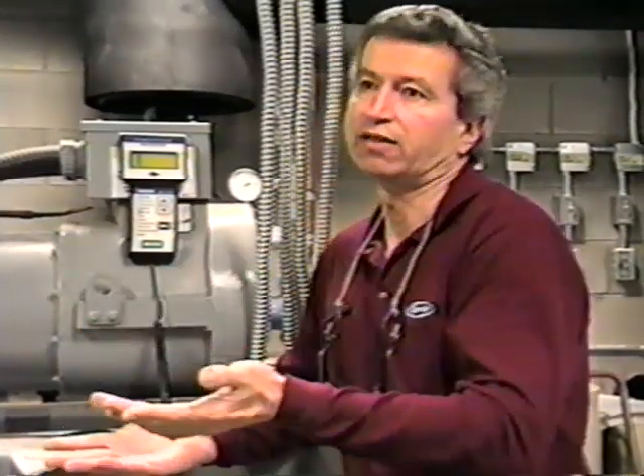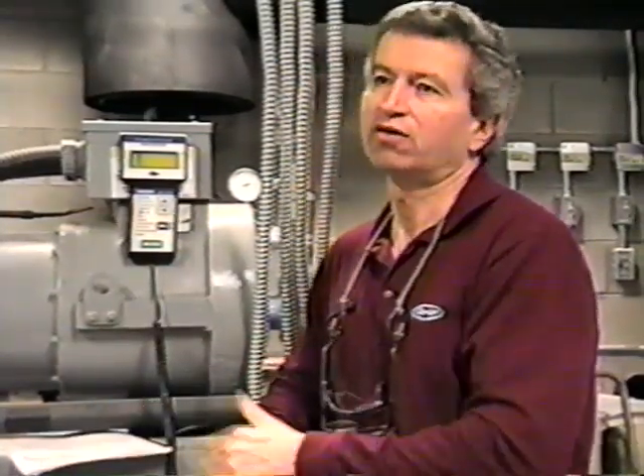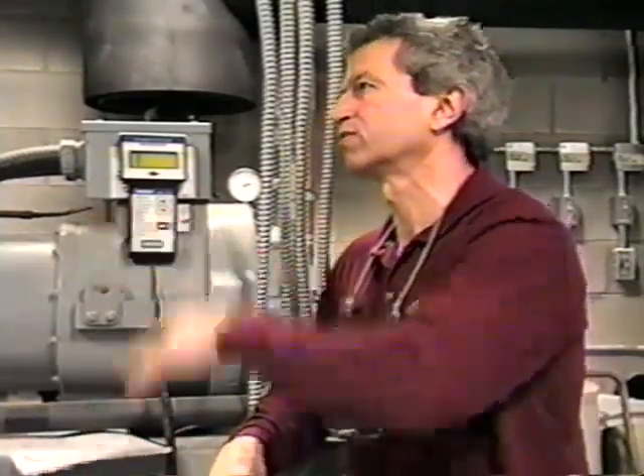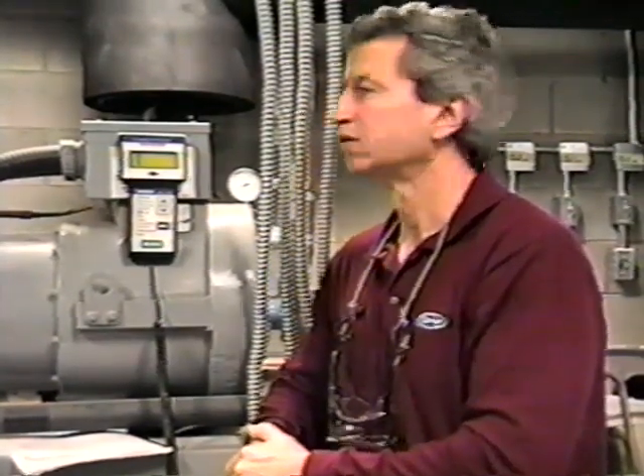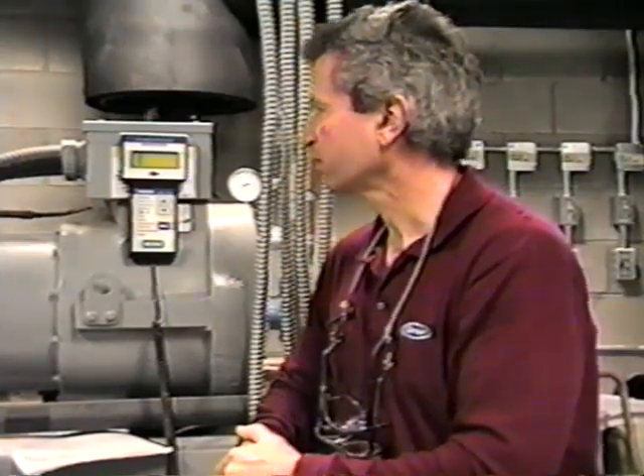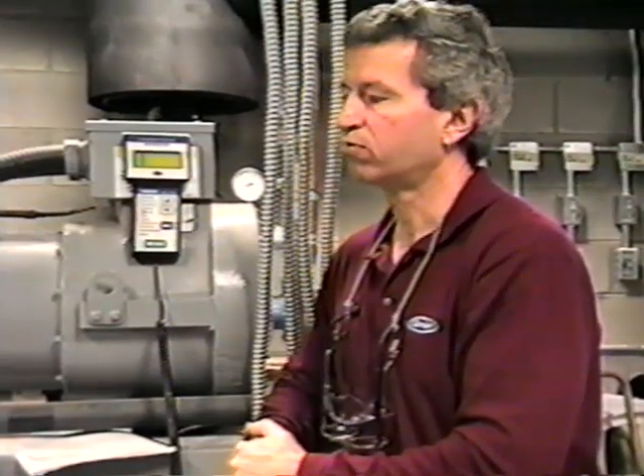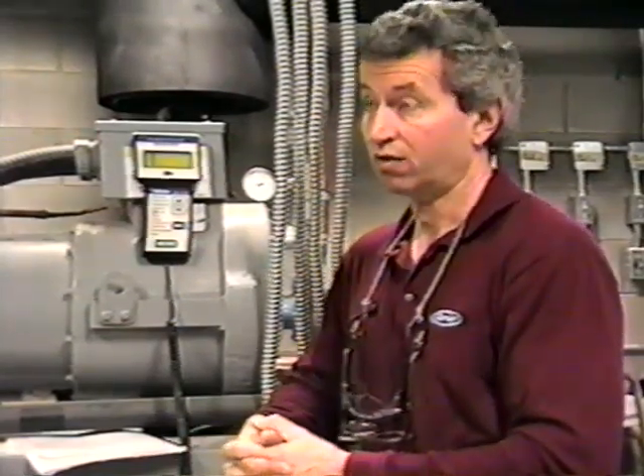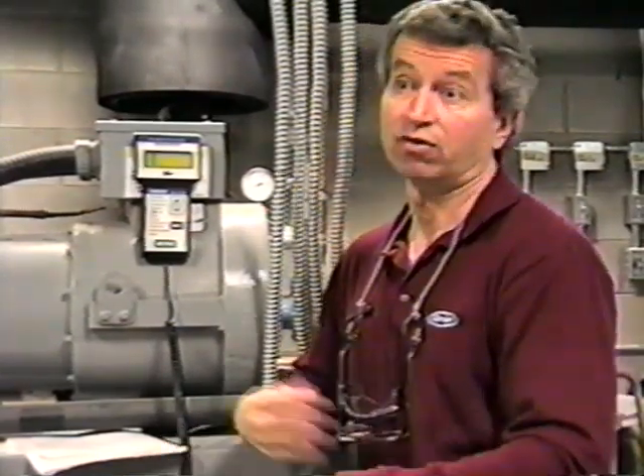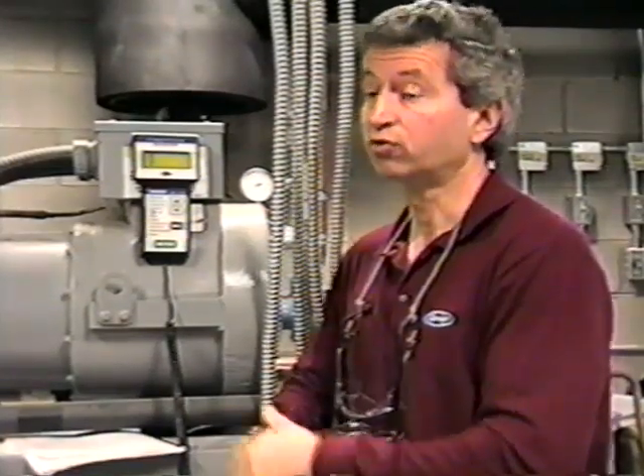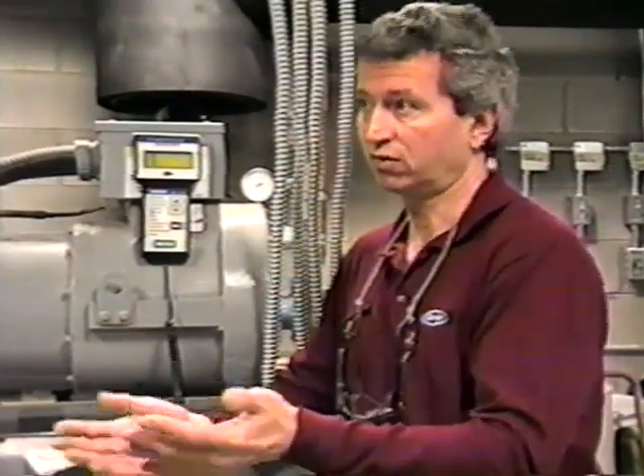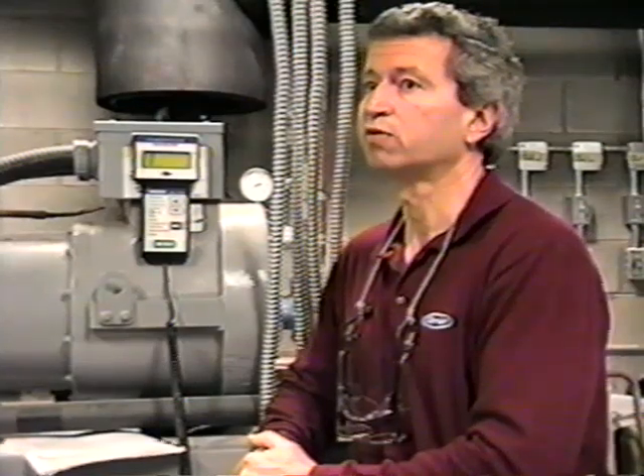Well, again, we're set for 90 degrees. Does it have to be 90 degrees? No, at the time of the startup, we really weren't set up 100%. You may be able to lower that, but that's really not a bad number to run at this point, especially during the winter. Like I said, it's probably going to help prevent some nuisance problems where you'll have that water go extra cold on you and drop that head pressure. You may run into oil pressure nuisance trips.